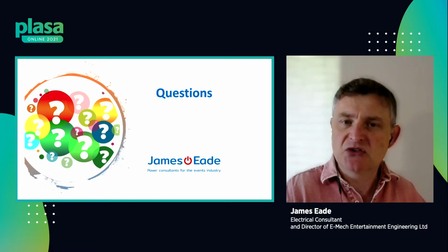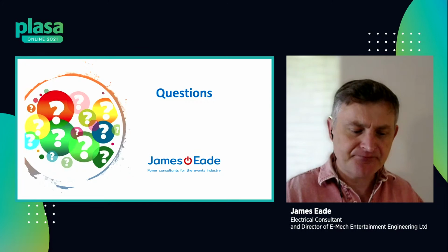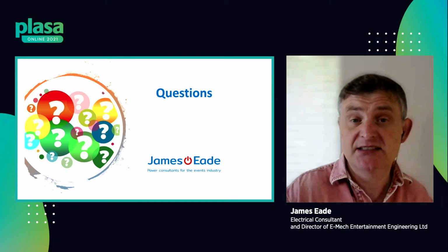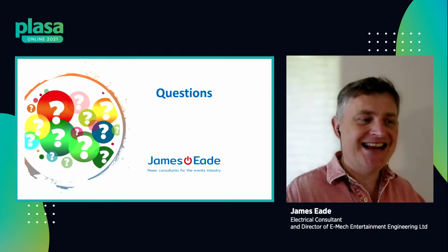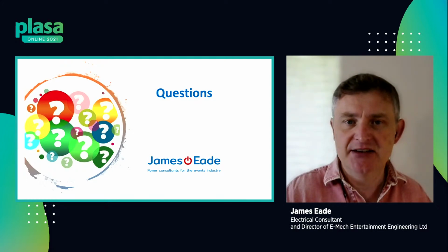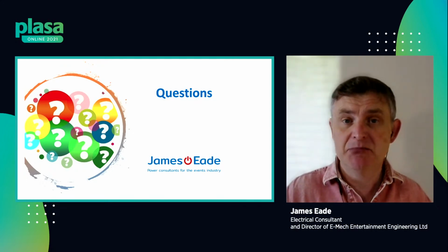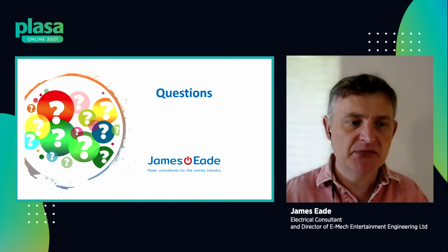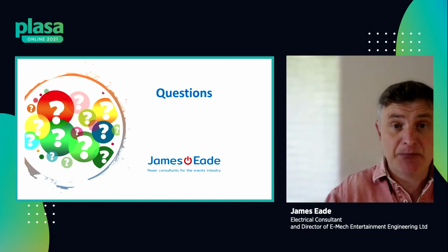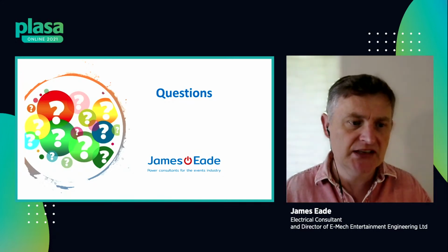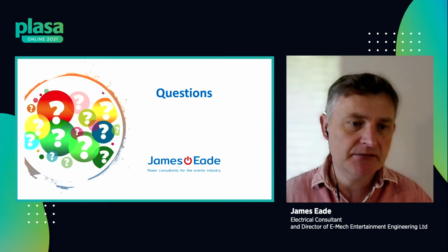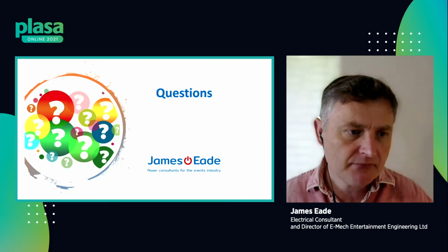So if you have an RCD that you think is behaving erratically, then you might want to do other tests to diagnose it. But the key thing is, in the event of a fault, will it disconnect and protect the user? And that's the key driver behind some of the forthcoming discussions and guidance that are happening in electrical safety circles. So that would be the prime one.